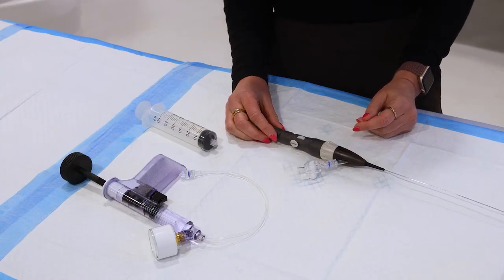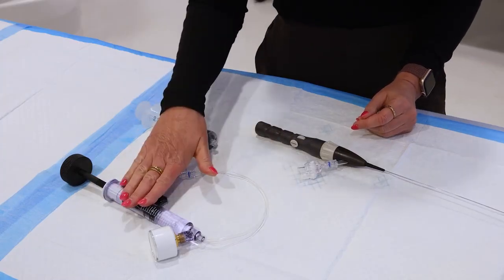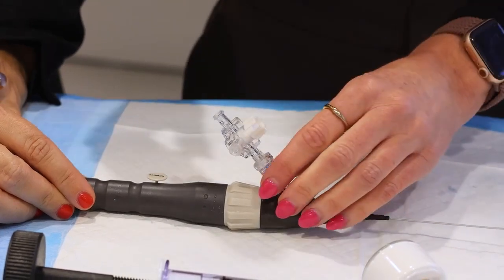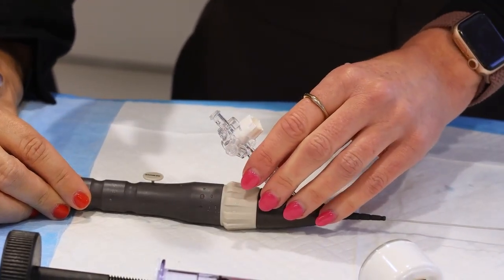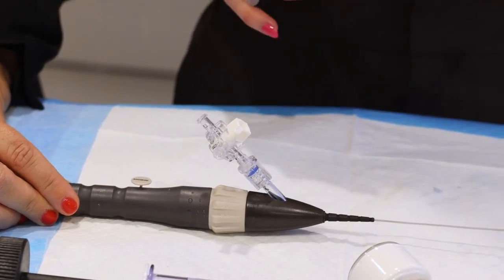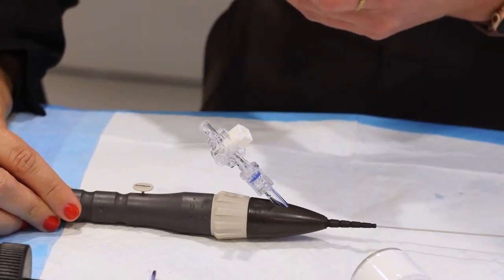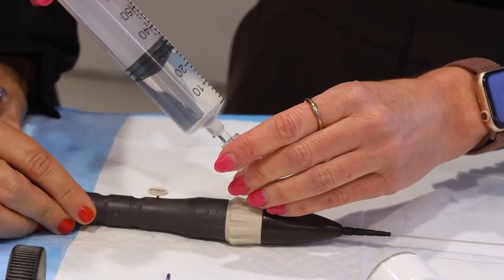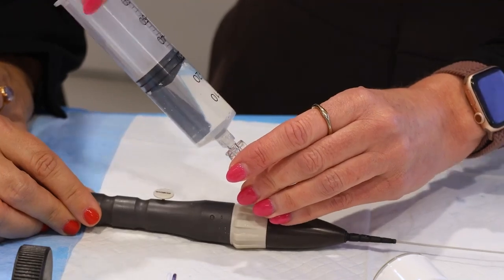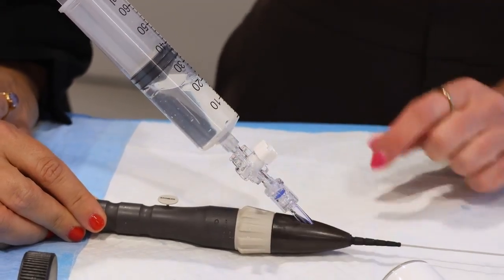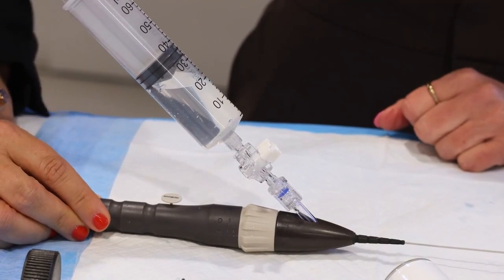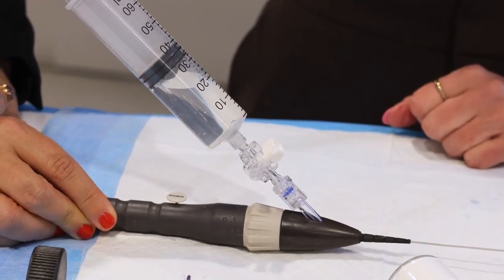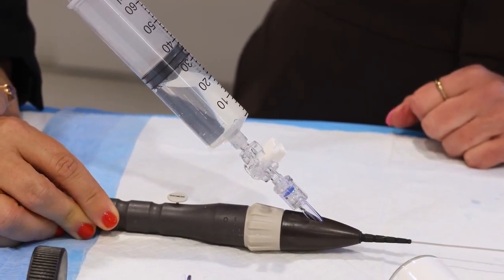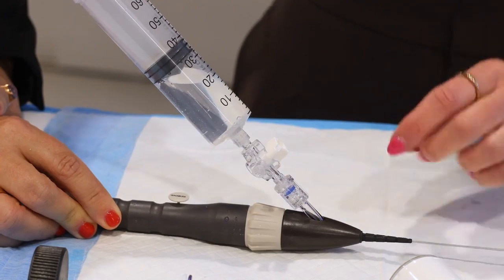Prepare an inflation device according to the manufacturer's instructions. Purge the air from the catheter using the inflation device syringe filled with 5 ml of the balloon inflation solution. Hold the syringe with the nozzle pointing downward and aspirate the lumen for 5 to 10 seconds. Repeat until no bubbles are seen during aspiration.